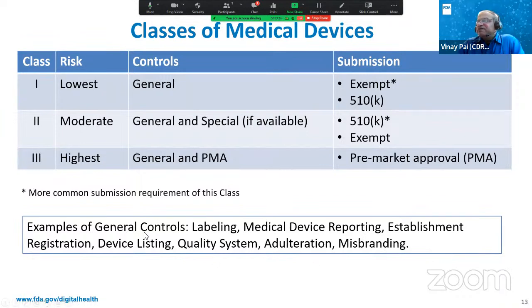At the bottom, I've listed the general controls, which are applicable even to the lowest class devices. You have to provide labeling for your device. Then you have to do medical device reporting. For example, if there are device-related injuries or deaths, you have to report that to the agency. Then you have to register your establishment with the agency and have a device listing, and you could use a global device IDs approach. Then you have to have quality systems in place to make sure the devices are safe and effective. And finally, we have to be able to track adulteration and misbranding concepts.